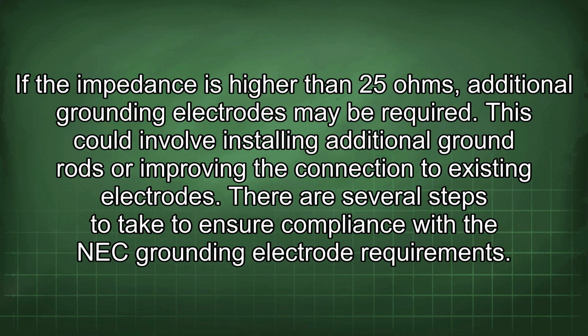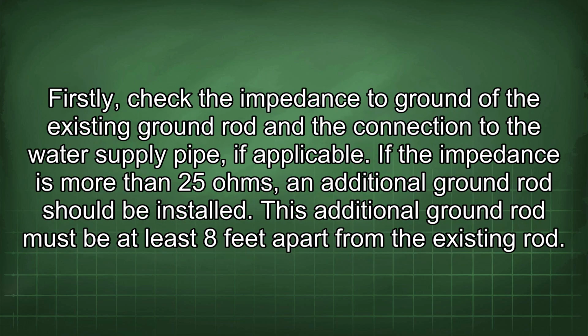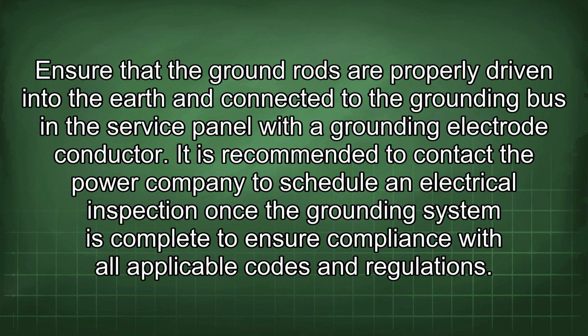There are several steps to take to ensure compliance with the NEC grounding electrode requirements. Firstly, check the impedance to ground of the existing ground rod and the connection to the water supply pipe, if applicable. If the impedance is more than 25 ohms, an additional ground rod should be installed. This additional ground rod must be at least 8 feet apart from the existing rod. Ensure that the ground rods are properly driven into the earth and connected to the grounding bus in the service panel with a grounding electrode conductor. It is recommended to contact the power company to schedule an electrical inspection once the grounding system is complete to ensure compliance with all applicable codes and regulations.